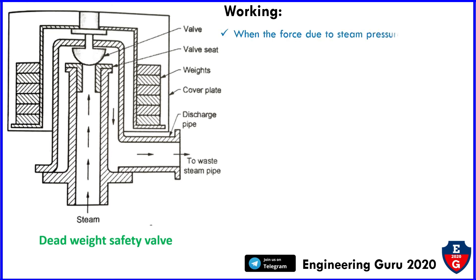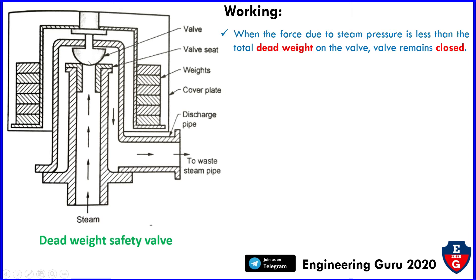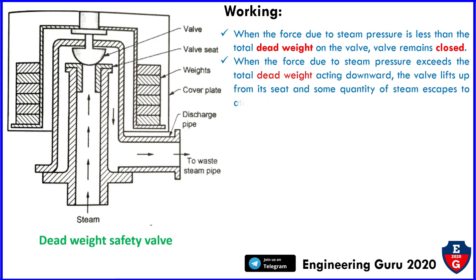Now we will see the working of the dead weight safety valve. When the force due to steam pressure is less than the total dead weight on the valve, the valve remains closed — as we can see in the figure, when pressure is less than the dead weight, the valve is closed. When the force due to steam pressure exceeds the total dead weight acting downward, the valve lifts up from its seat and some quantity of steam escapes to the atmosphere through the pipe. We can see the steam: when the steam pressure exceeds the dead weight, the valve lifts up like this.